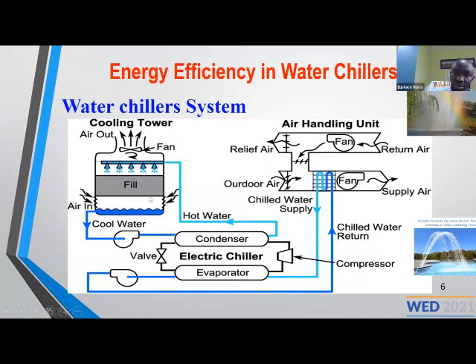You can use VFDs on these fans and the pumps, so that if it's water, you don't have to pump a lot of water when it is not needed, when the outdoor temperatures are a bit low. So you can use the VFD to control the speed of the fans and the pumps, so that you reduce the amount of energy being consumed, especially when the outdoor air is cool. For example, you want 20 degrees inside, like in a data center, and you find that air is coming in at 21. You don't require a lot of water to cool from, say, 21 to 20, compared to if the outdoor air was 25. So you need to be monitoring that.